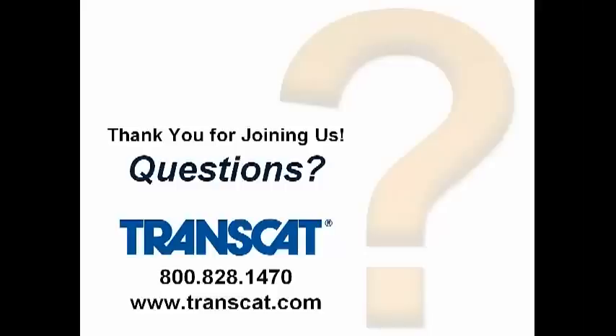Okay. Next question is, do you see one type of error over other types of errors? I assume that's about those 10 categories. It's surprising to me how often an instrument is not selected correctly for suitability for the intended purpose. One of the things that I always ask a client when they're talking about an instrument is, what are you trying to do with the instrument? Where are you using it? What are the production tolerances or the testing tolerances that it's being used against? Start with that. Understand where it's being used to make sure that suitability is correct, and make sure that instrument is capable of producing valid results for that type of measurement and for those tolerances. So that's one area that I'm a little surprised that I see problems with.